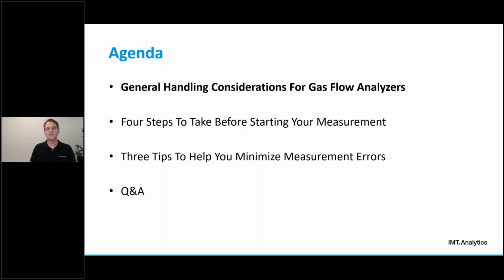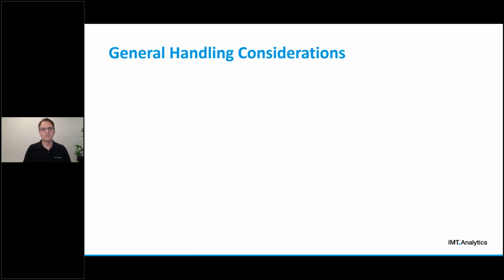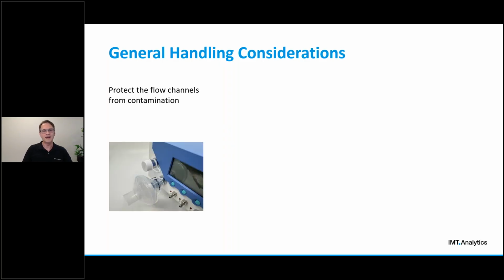Okay, so let's kick things off with some general handling considerations for gas flow analyzers. To ensure accurate measurement and guaranteeing longevity of your gas flow analyzer, there are 3 general handling considerations I would like to share with you. The first one is to protect the flow channels from contamination by applying the protection caps. You can see one here in this picture on the flow channels whenever they are not in use, and to always use the included dust filter in front of the flow channel when a flow channel is in use. This is really crucial for all gas flow analyzers in the market. Please also ensure that you have a dedicated filter for your analyzer and that you never use it in reverse direction, meaning that the dirt side is facing the flow channel of your analyzer.